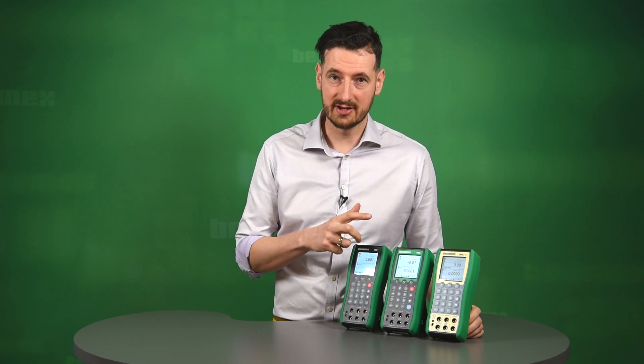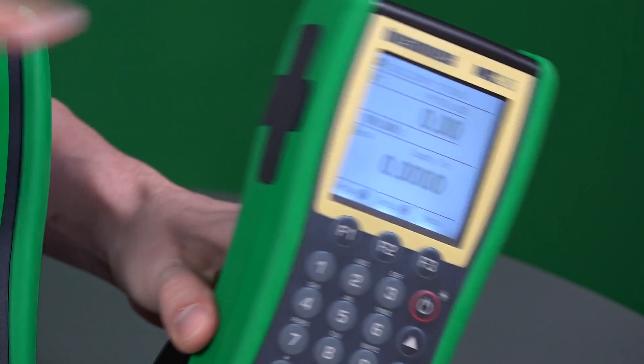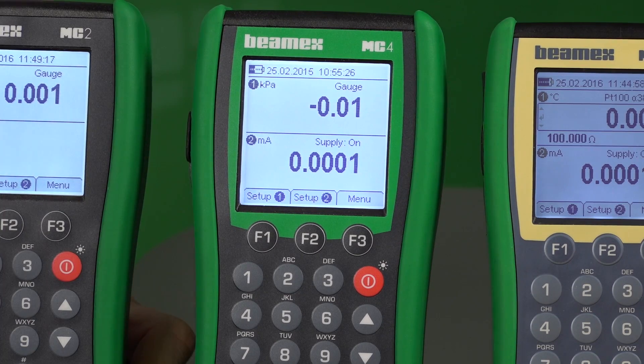The MC2 and MC2IS share exactly the same functionalities. When you are in a hazardous area, you may want to consider using the MC2IS — it's an intrinsically safe unit with the same capabilities as the MC2. It has got built-in power supply for a two-wire transmitter and can also measure external pressure modules by connecting on the side. The MC4 has two distinctive differences: improved accuracy on thermocouple, RTD, and pressure.